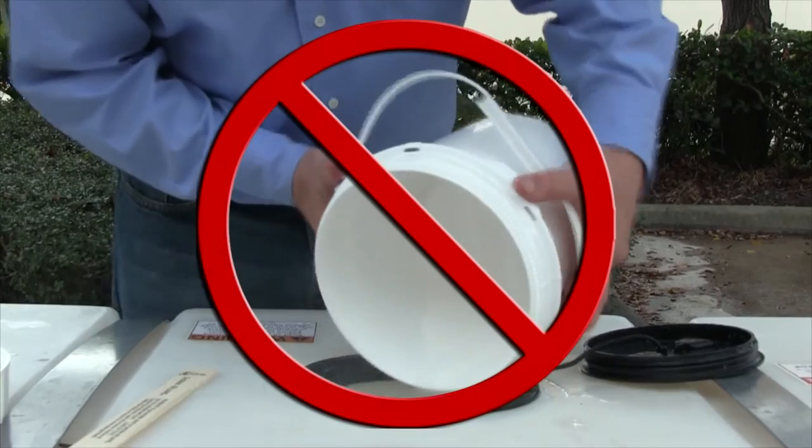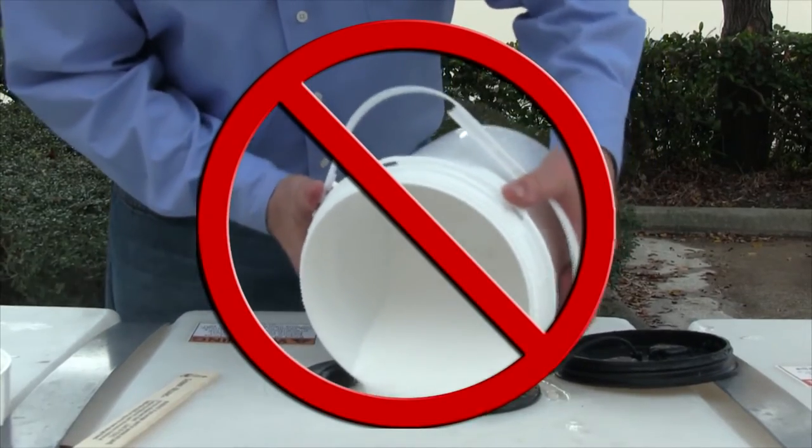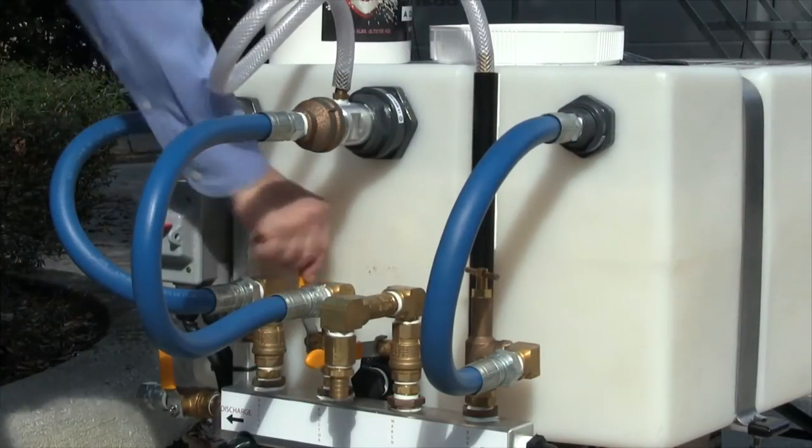Over a period of approximately five minutes, introduce three-quarters of the Fire Ice Shield bucket into the tank using the eductor pickup tube. Move the pickup tube in a slow circular motion around the bucket. Do not force powder into the system.